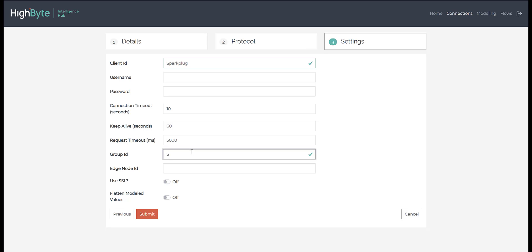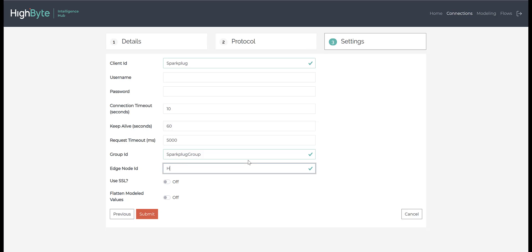You will also need to add the Sparkplug group ID and Edge node ID. The group ID identifies a collection of Sparkplug nodes, while the Edge node ID specifies a unique node within this group. Just like MQTT, you can also choose to leverage SSL or flatten model values before publishing the results.